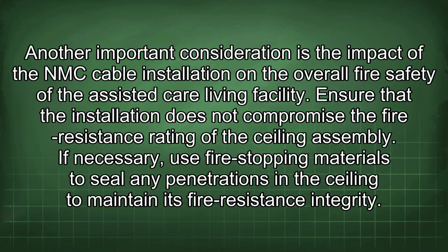Another important consideration is the impact of the NMC cable installation on the overall fire safety of the assisted care living facility. Ensure that the installation does not compromise the fire resistance rating of the ceiling assembly. If necessary, use fire-stopping materials to seal any penetrations in the ceiling to maintain its fire resistance integrity.